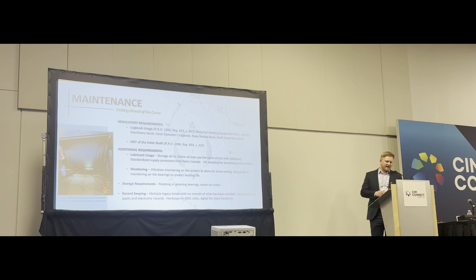Baseline measurements, so your vibration, your temperature, all those proactive measurements, you need to be able to come back and compare to that. When you have an incident, you have a maintenance issue, you don't actually know what you're measuring against. This could be years down the line. With those baselines, you always know what it should be. Again, I've seen that a lot of times where you don't have baseline measurements and you pick up a random vibration somewhere, certainly with electrical, and it's a nightmare.